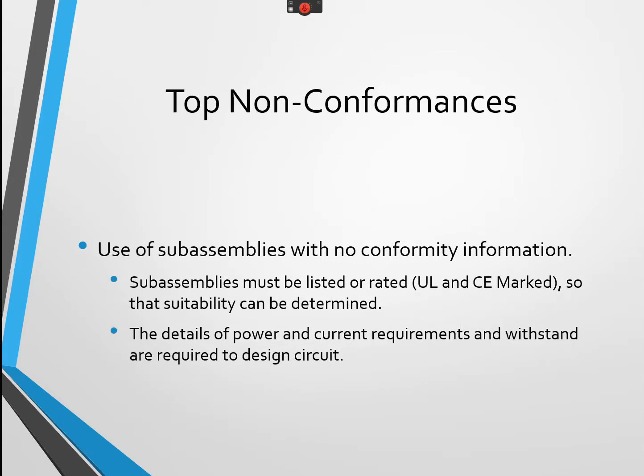Use of subassemblies with no conformity information. If you're going to include a subassembly that uses line voltage, and you expect to get your equipment field labeled, it does absolutely need to be listed and marked. And we need to be able to determine that it's actually listed. We recently did a project, the piece of equipment, it was a transformer, and it said NRTL listed on the transformer. As soon as I read that, I know it's not NRTL listed, because if it was, it would have the symbol of an NRTL there, and it would include the data required. And then also for these subassemblies, we need the power and current requirements so that we can design the circuit and the overcurrent protection.